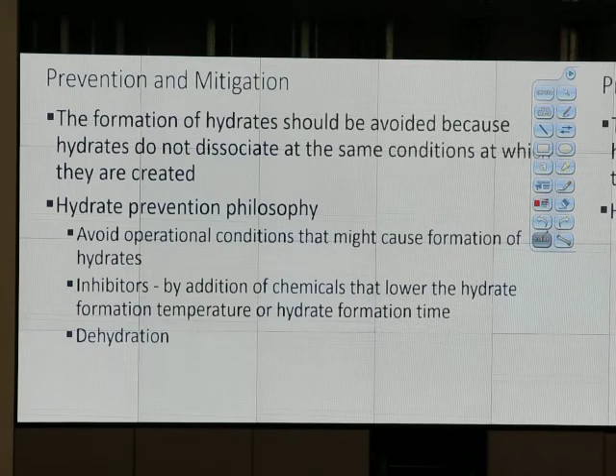Even though we have hot gas, gas temperature can drop a lot if we choke it. You agree? If I have flow through a choke, pressure drop a lot and also temperature drop a lot. JT cooling, right? Joule-Thomson cooling. So even though you don't have hydrate to begin with, the gas is hot, but when it goes through the choke, pressure drop a lot, then we have Joule-Thomson cooling. Then the temperature can be within the hydrate phase envelope.